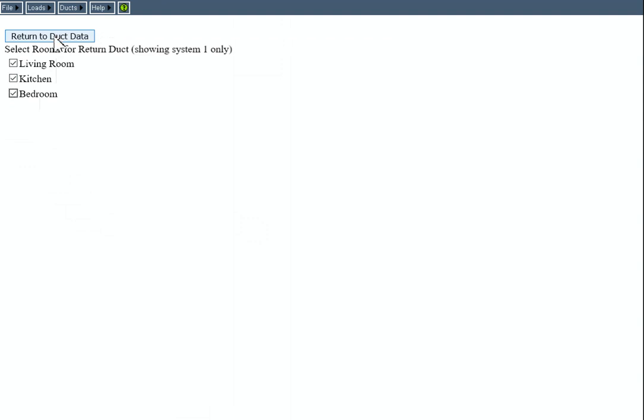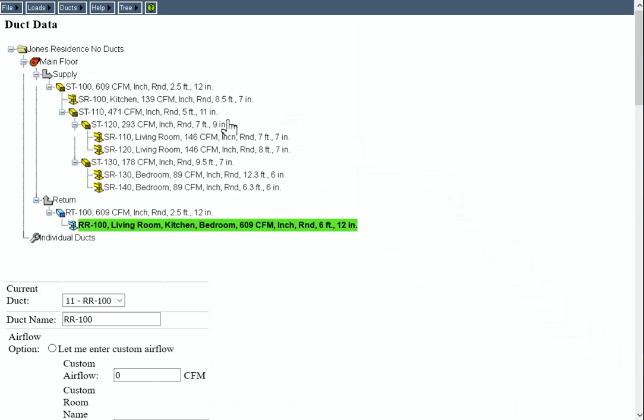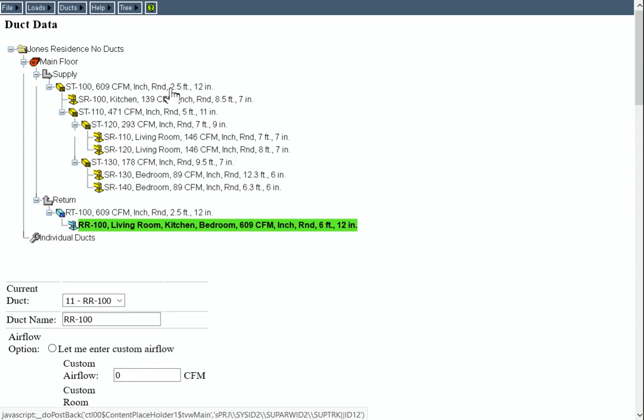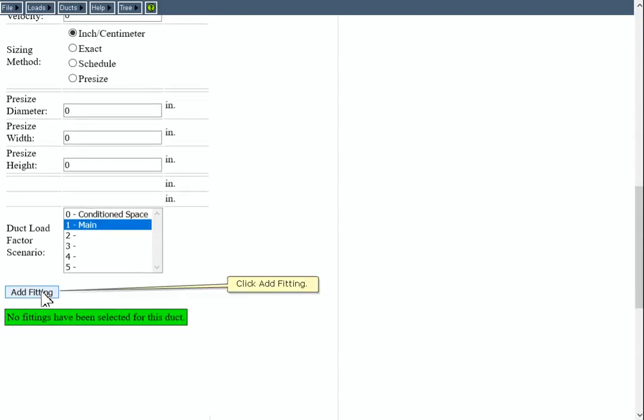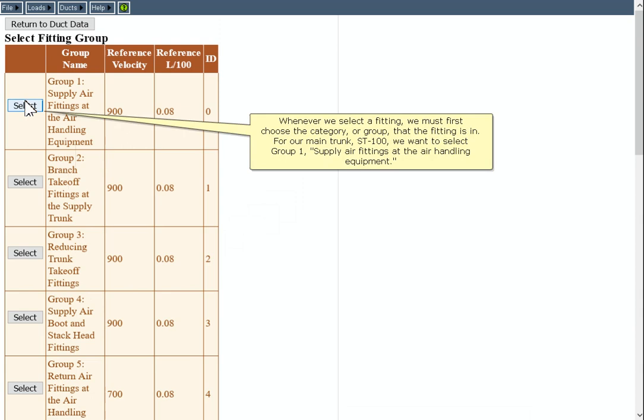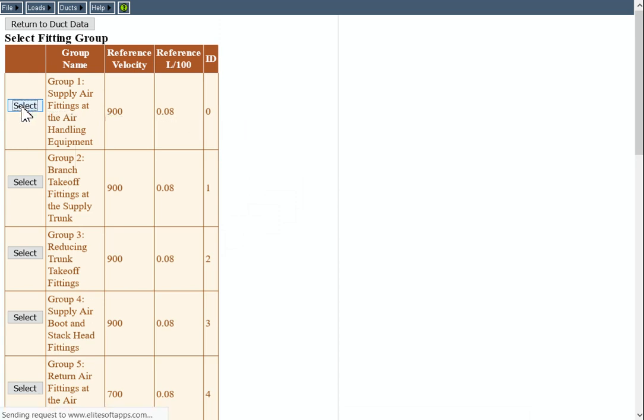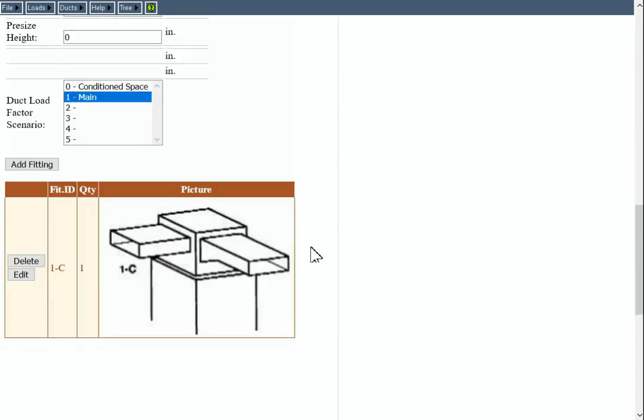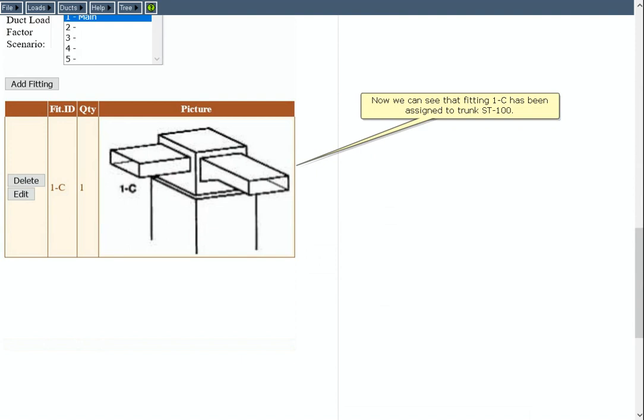In order for the program to give us accurate pressure loss results, we need to be sure to assign fittings to the ducts. Start by clicking Trunk ST100. Click Add Fitting. Whenever we select a fitting, we must first choose the category or group that the fitting is in. For our main trunk ST100, we want to select Group 1, Supply Air Fittings at the Air Handling Equipment. The fitting with ID 1-C happens to match what we want, so click its Select button. Now we can see that fitting 1-C has been assigned to Trunk ST100.